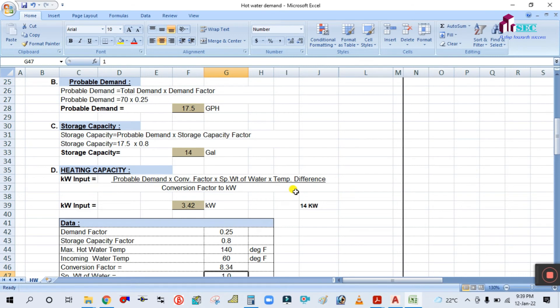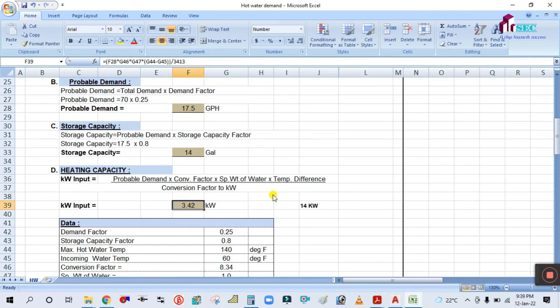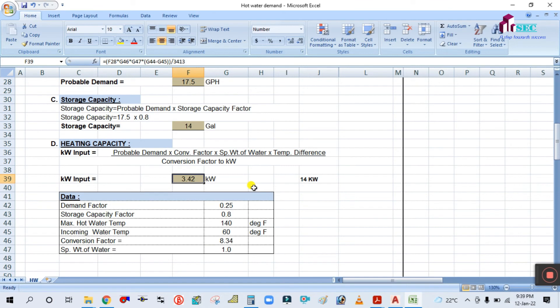Heating capacity in kilowatts = probable demand × conversion factor × specific gravity of water × temperature difference, divided by the conversion factor to kilowatt (3413).